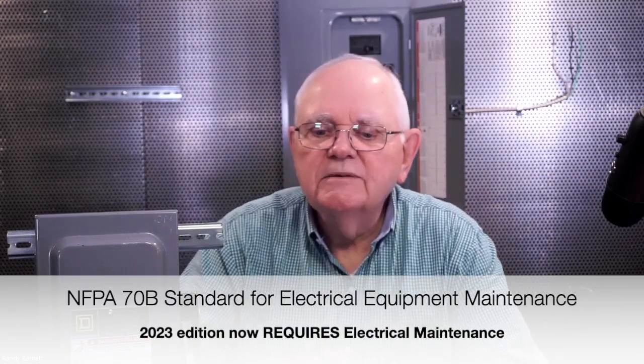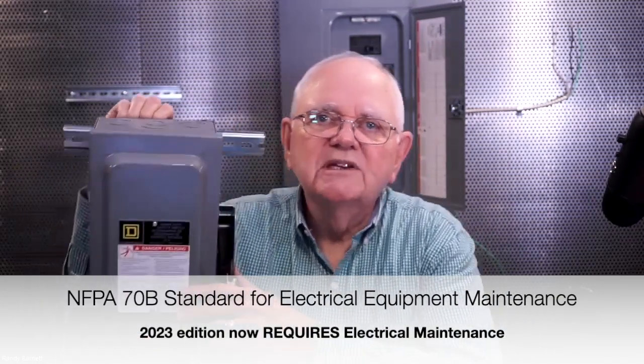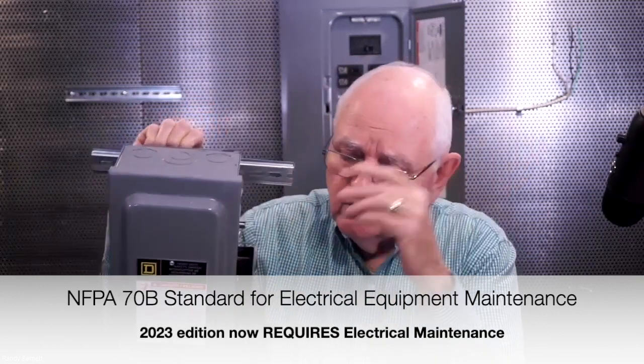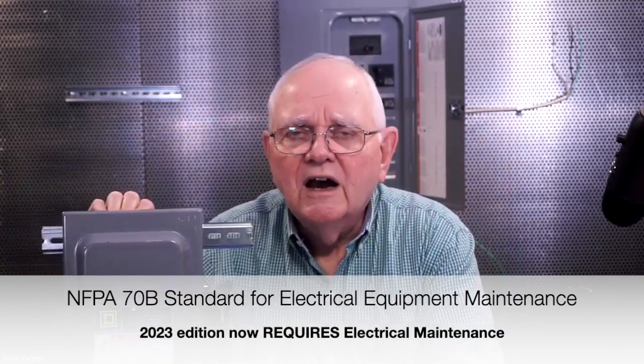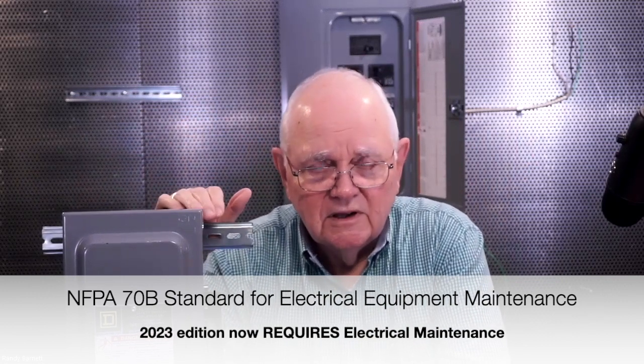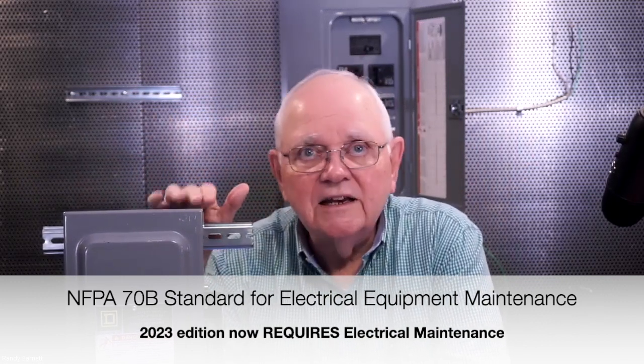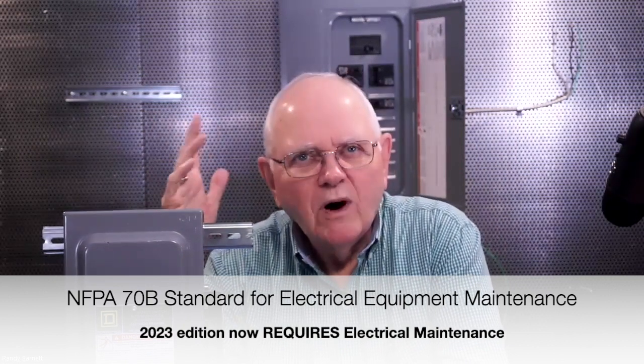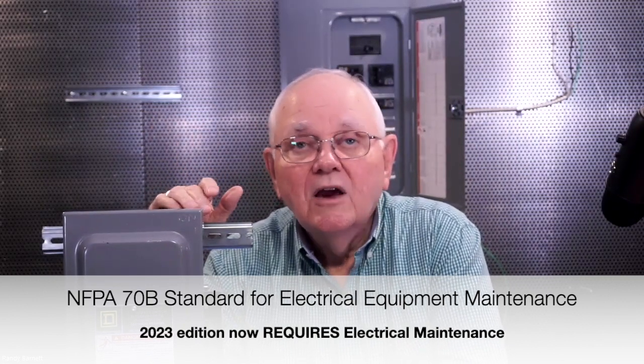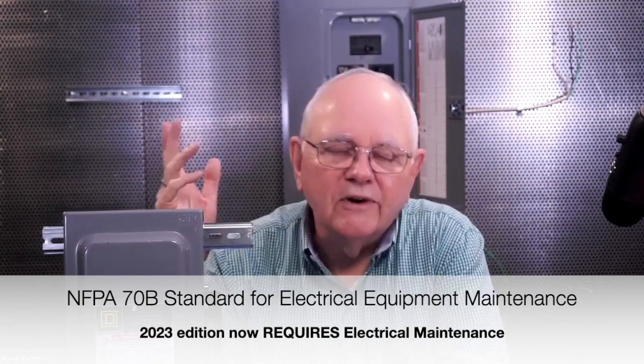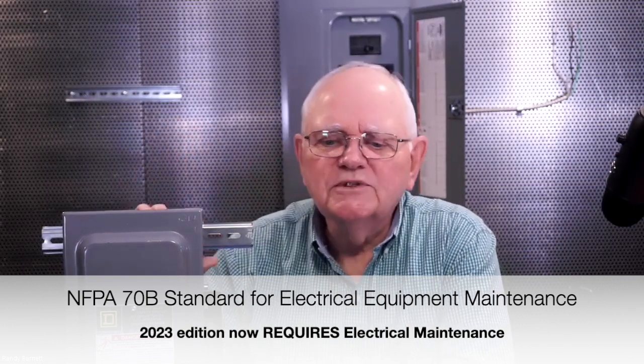One last thing we can mention is maintenance. NFPA 70B is no longer a recommended practice for electrical equipment maintenance. It is now a standard for electrical equipment maintenance. That means the maintenance we do on our disconnecting means and safety switches, UL 508s, whatever we're using, is something we have to do. How often do we do maintenance? We'll find that in the NFPA 70B standard. What types of maintenance do we have to do? It divides it up by whether or not the equipment is operating and so forth, but basically, when it comes to disconnecting means, there are some different things you need to look at.